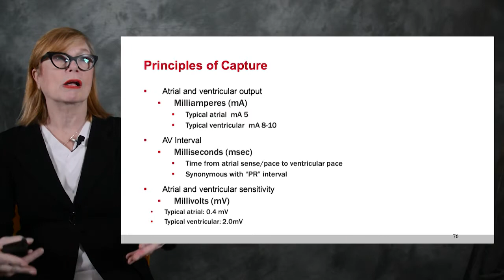If my patient fires his own beat, and he fires his own beat in the atria, it must be higher than the millivolt signal that I've set in order to have set the sensitivity for sensing of the pacemaker. And if it fires into the ventricle, it has to have an impulse of around 2 millivolts in order to have the sense of the ventricular beat. Sensing the beat inhibits the pacemaker from firing until the next cycle time.